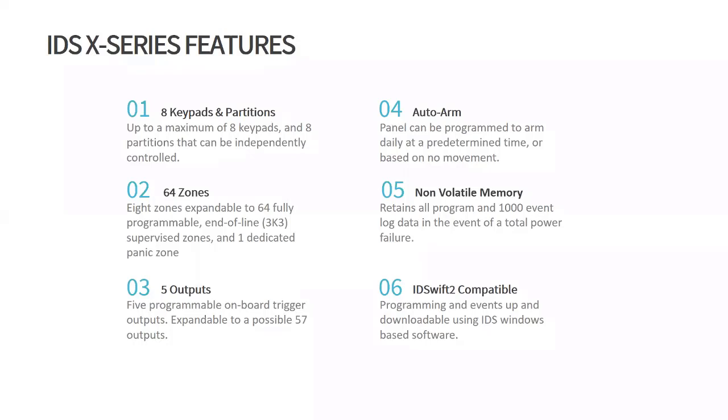The Auto-ARM panel can be programmed to arm daily at a predetermined time or based on no movement. Non-volatile memory retains all programs and a thousand event log data in the event of total power failure. It is IDS Swift 2 compatible, allowing programming events to be uploaded and downloaded using IDS Windows-based software. Note: if you're using IDS Swift 2, you do need the hype modem to connect to the units.